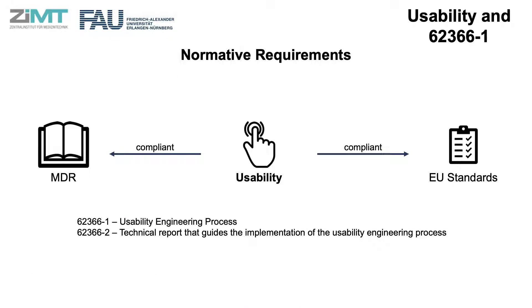By looking at the state-of-the-art of European standards related to usability of medical devices, particular attention should be paid to the standard IEC 62366-1. The first part of the standard is dedicated to the usability engineering process, and the second part is a technical report that guides the manufacturer on the practical application, methods and analysis of the usability engineering process for medical devices. We will now describe the first part of the standard. Relevant sections of its paragraphs are written in brackets.